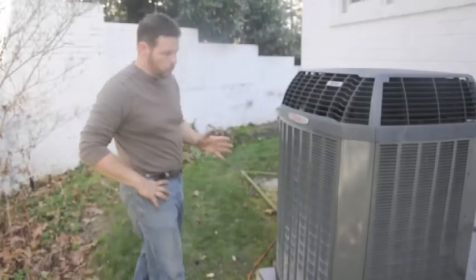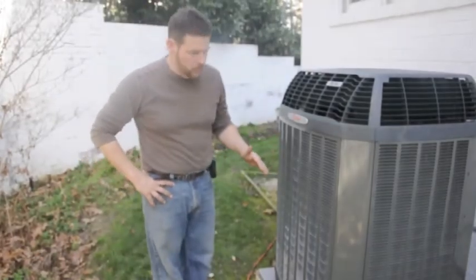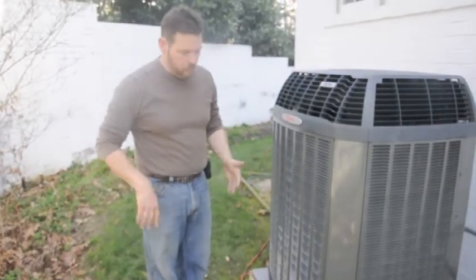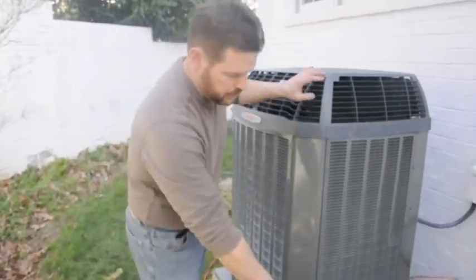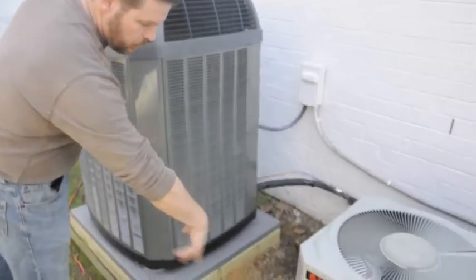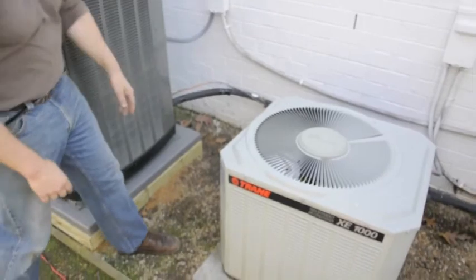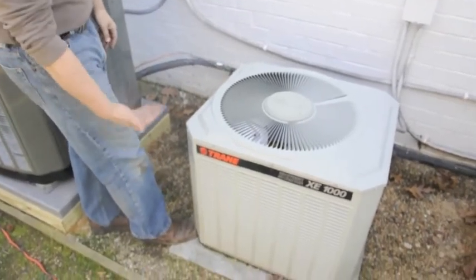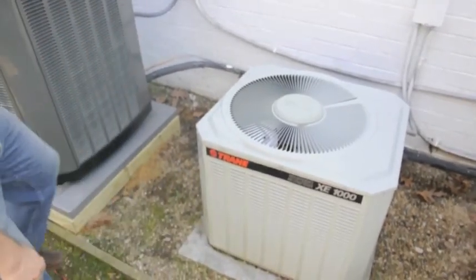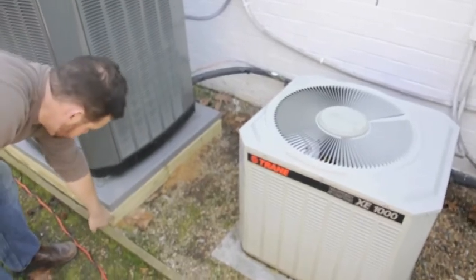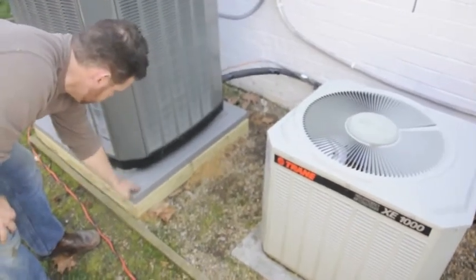Okay, what we've done with the outdoor unit is, when we install an outdoor unit, we want to raise the unit off of the ground level. As you can see, this one here has tilted back. It wasn't level. It's not raised off of its actual pad. So we'll actually build a foundation, a treated foundation, condenser pad.